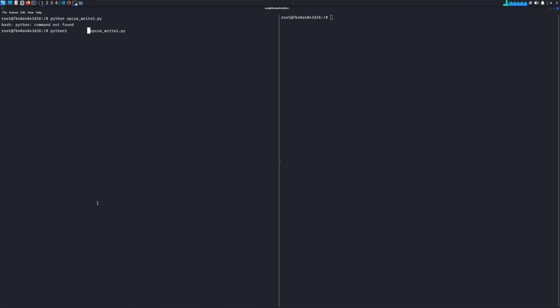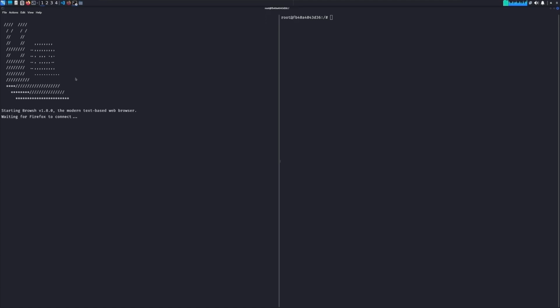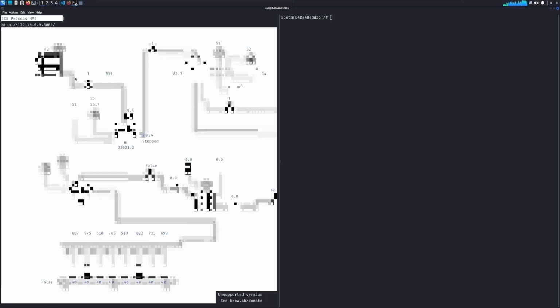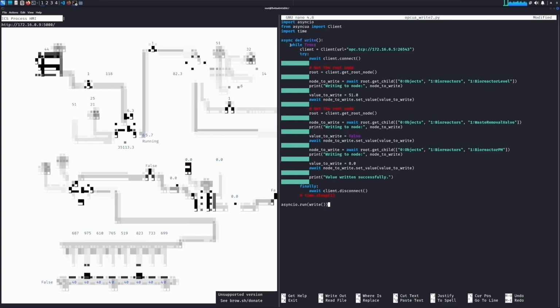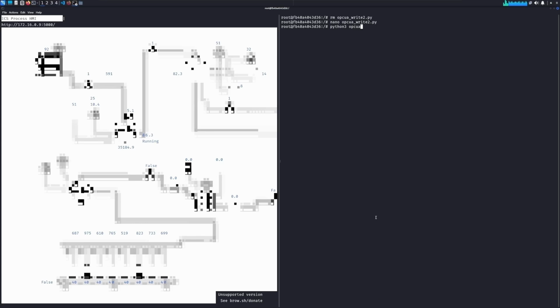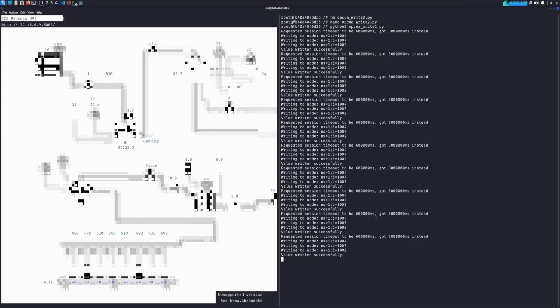Now running the OPC UA script again to see if we manage to write our values. Checking the HMI to confirm the values are modified. All the other values are changed, but the waste removal valve is not set to false. It seems it is being reset, as the ideal conditions are not met. To counter it, modify the script to write these values over and over again using a while loop. Run the modified script and check the HMI for changes.